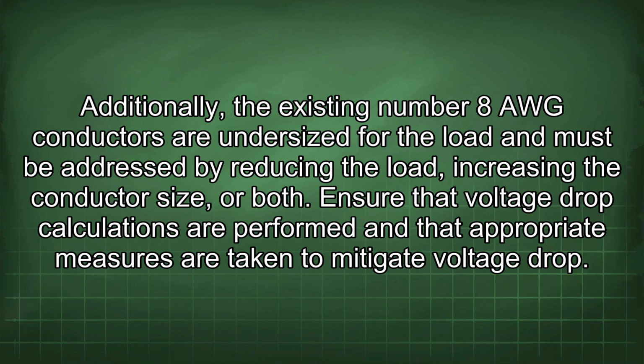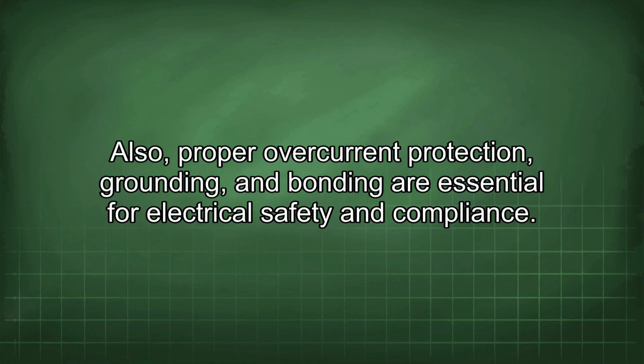Additionally, the existing number 8 AWG conductors are undersized for the load and must be addressed by reducing the load, increasing the conductor size, or both. Ensure that voltage drop calculations are performed and that appropriate measures are taken to mitigate voltage drop. Also, proper overcurrent protection, grounding, and bonding are essential for electrical safety and compliance.